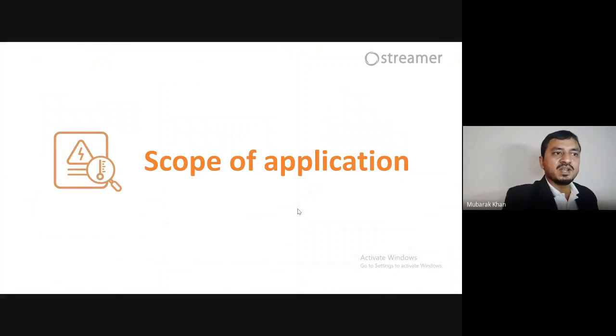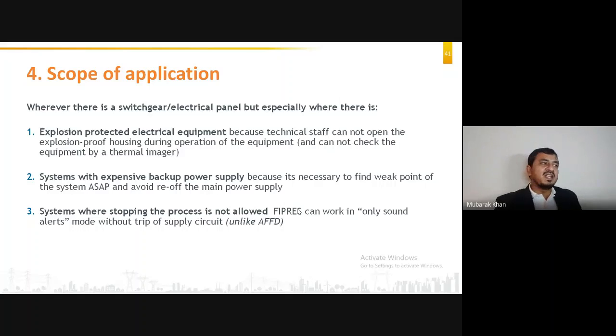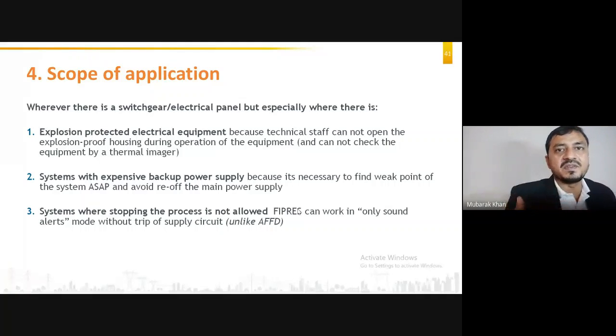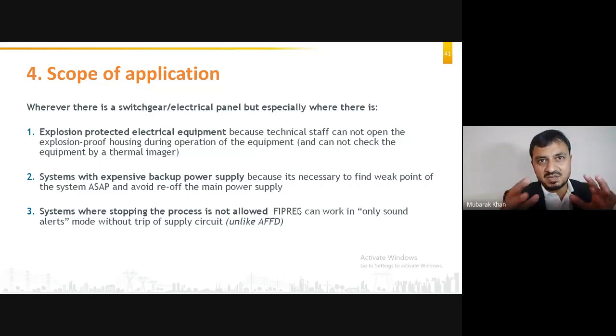Okay, scope of application of the remote. Remote monitoring is normally required when you cannot open the panel, or your systems are really expensive. Then you will need remote monitoring. Otherwise, in most cases, thermography will do, or you can simply avoid it because the system is very small. If your backup power supply is feeding a load where continuity of power supply is very important, then you must use a system like this. Or if your equipment itself is very expensive, any damage can cause a very heavy financial disaster. Anyway, if you install continuous monitoring, you'll have to spend money, so you need to see if it is value for money only.